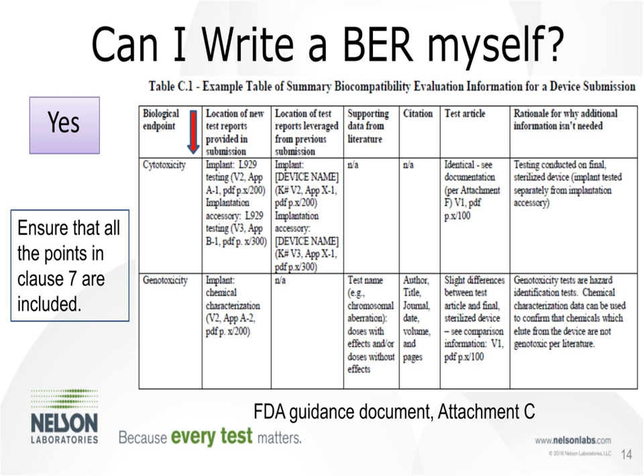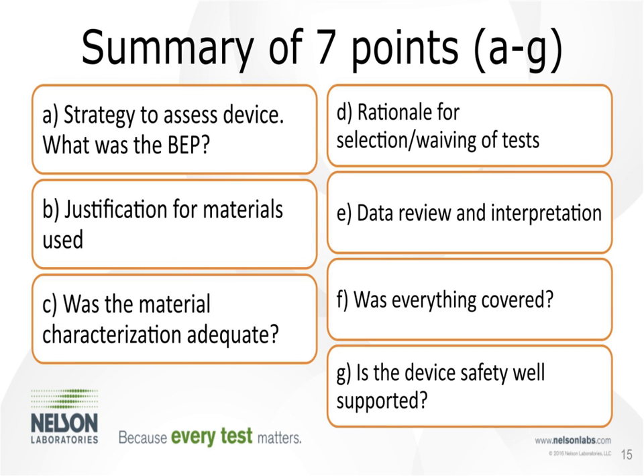Can you write a BER yourself? Yes, of course you can. The FDA guidance document Attachment C lists an example summary table for a biocompatibility evaluation, organized by biological endpoint. However, the ISO guidelines indicate they're looking for more than just biological endpoint information, so if you write your own BER, ensure all the points in Clause 7 are included. To summarize the seven required points: a strategy to assess the device, justification for materials used, adequacy of material characterization, rationale for selection or waiving of tests, data review and interpretation, identification of any gaps, and whether device safety is well supported.